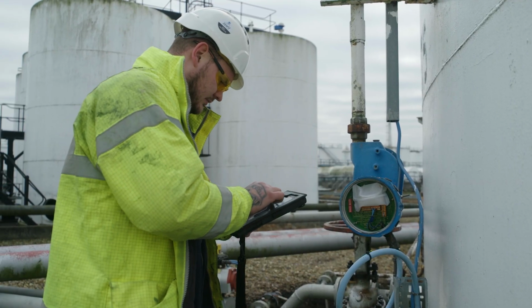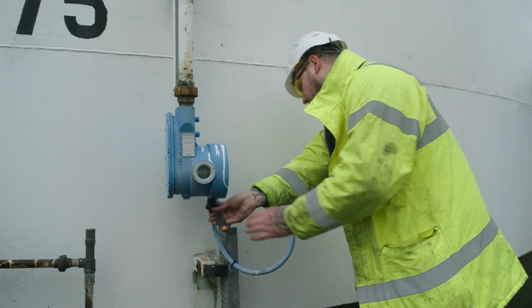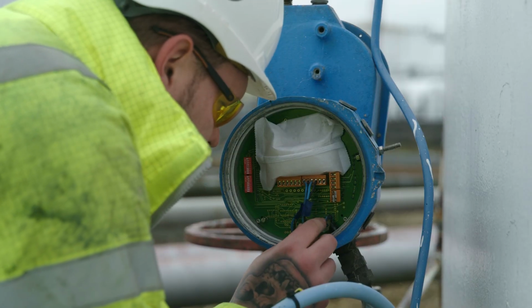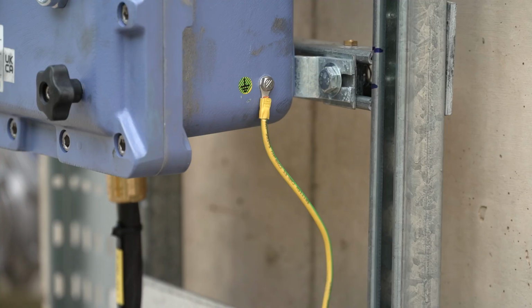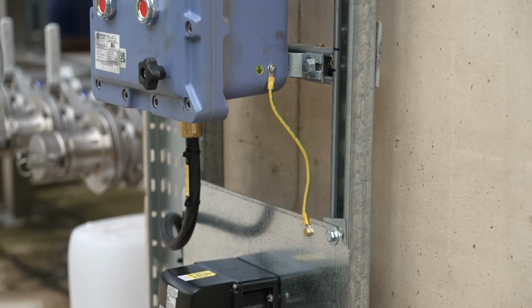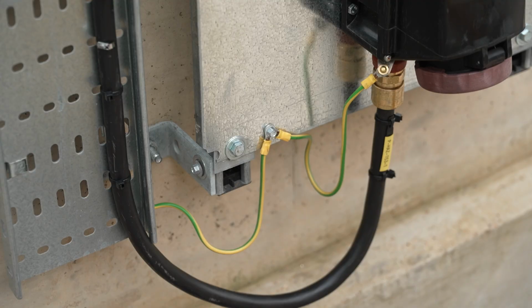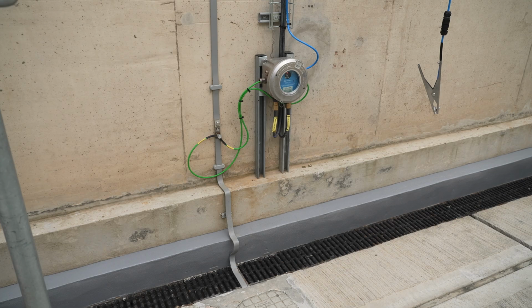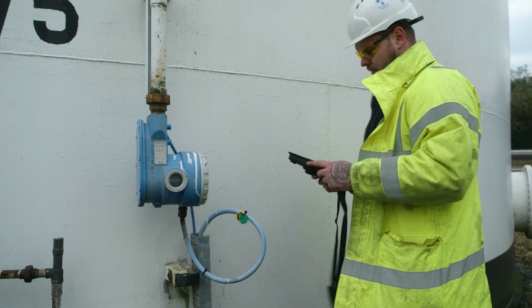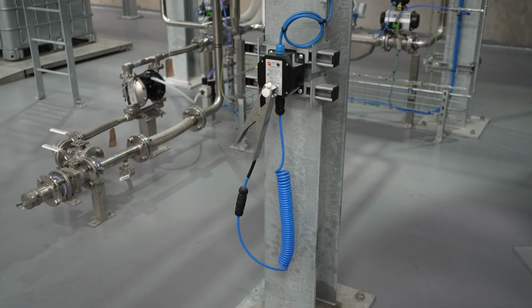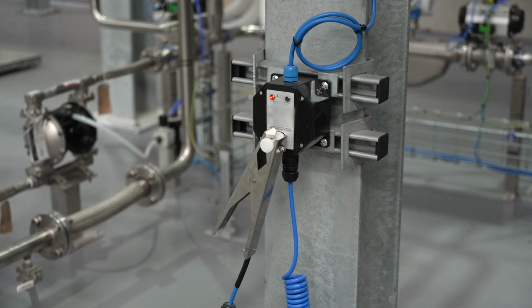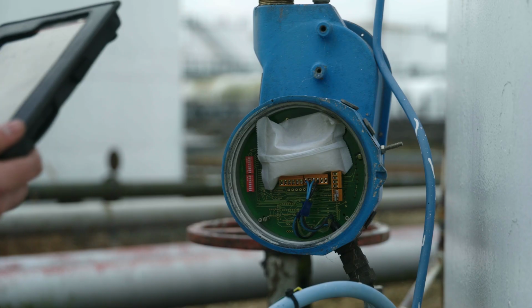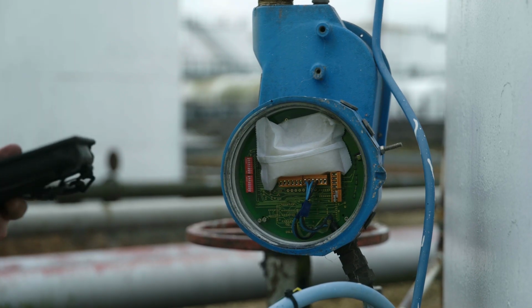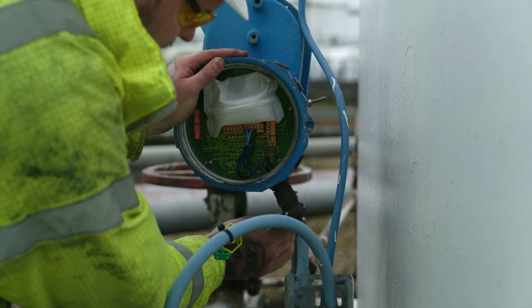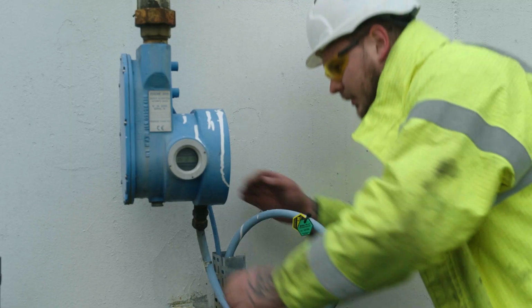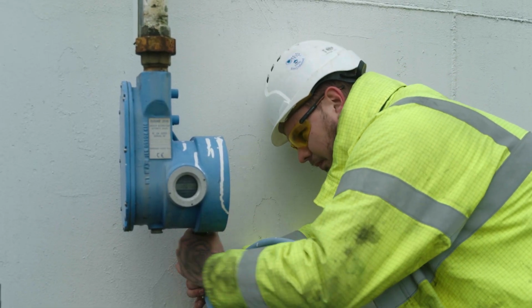To maintain a high level of static electricity awareness, regular testing of equipment must take place, with results logged. Operators should be trained frequently with reference to the appropriate standards and industry best practice. The fixed part of the earthing system should be tested by a specialist authorized contractor, typically every 12 months. Earth leads and clamps for portable equipment should be tested more frequently depending on the nature of the application. Operators should be vigilant for deterioration of equipment between test periods, such as worn cables or broken clamp teeth. Report any suspected faults prior to further use.